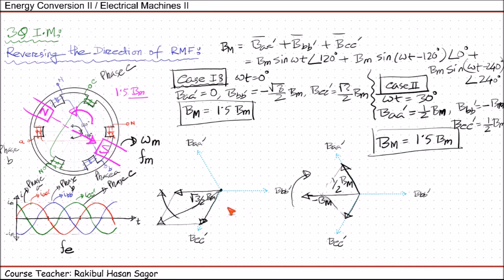This is a very important phenomenon and will play an important role when we change the direction of the rotor of an induction motor. If we can change the direction of the rotating magnetic field, we will be able to change the direction of the rotor as well. By changing any two phases of the three-phase supply, we can achieve this. We will start the rotor construction of an induction motor in the next lecture.